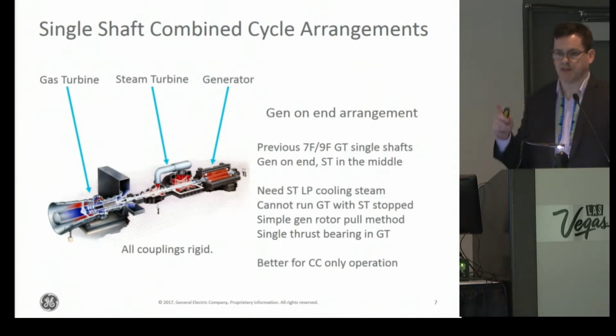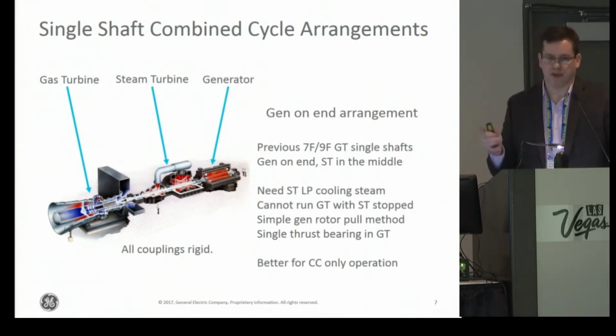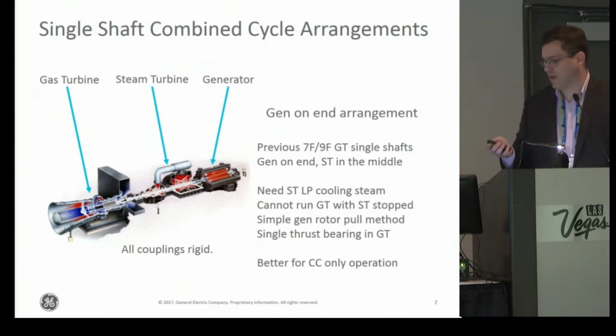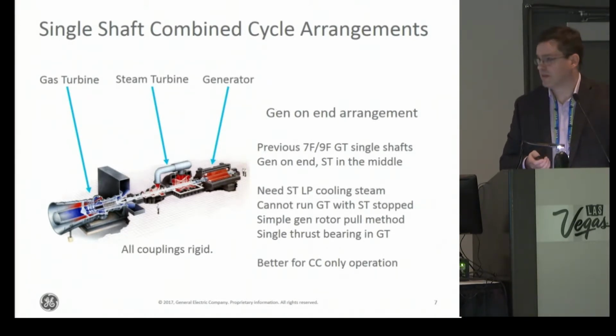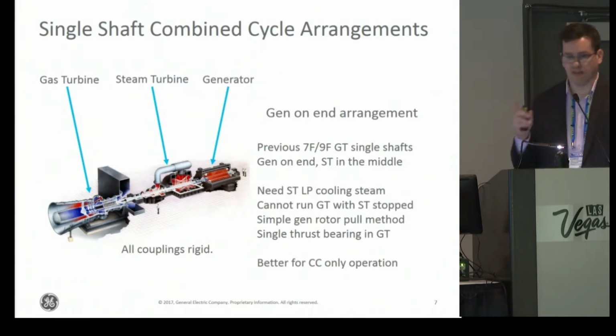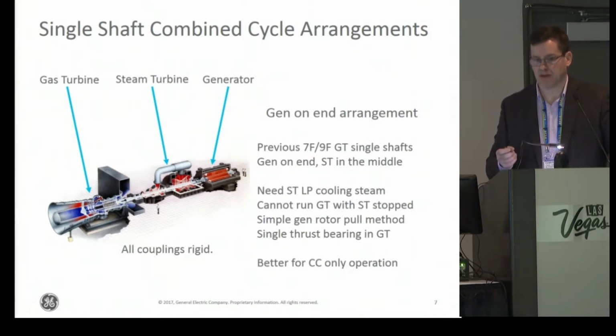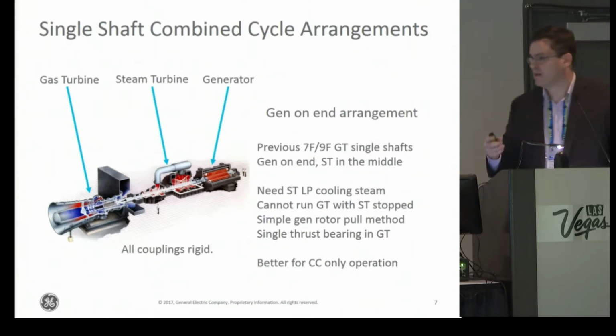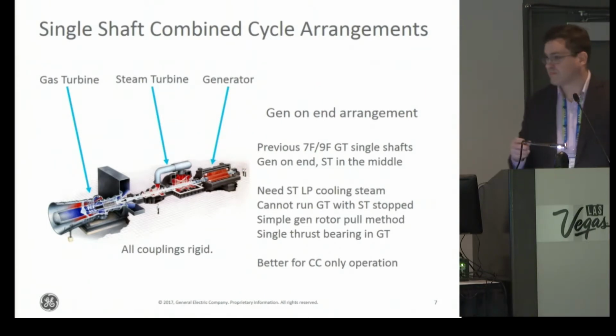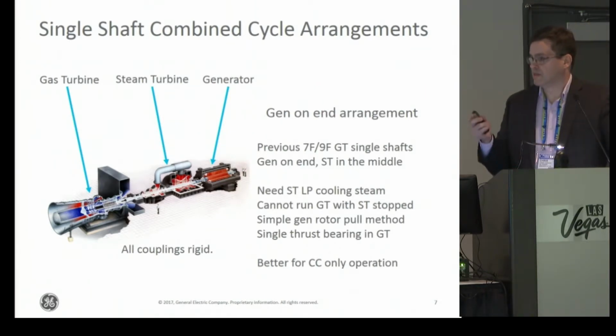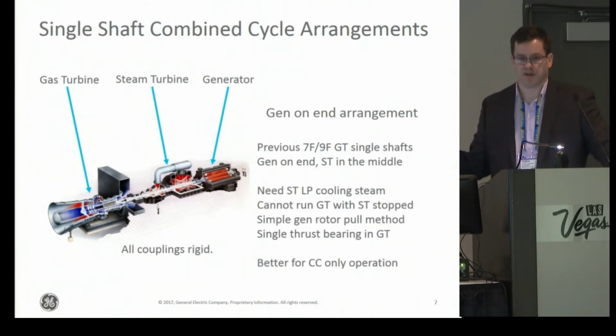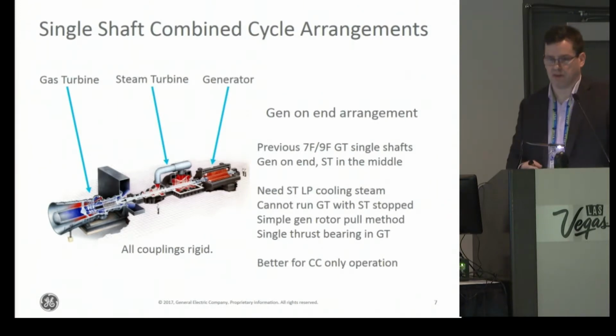This is the configuration, steam turbine in the middle, that dominated most of GE's F-class single shafts, where you have the steam turbine between the gas turbine and the generator. This is a really simple arrangement. You only have one thrust bearing. That's in the gas turbine, and it carries the full thrust load of the train. The steam turbine transmits torque from the gas turbine down to the generator. This is also easier, as I was saying before, for generator maintenance. You just pull that generator field out the end of the generator when you want to take the unit apart.